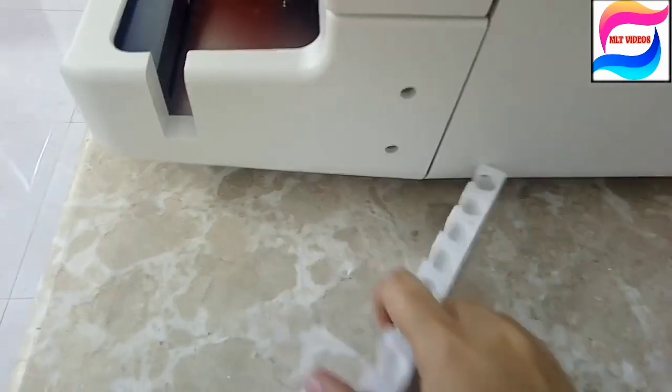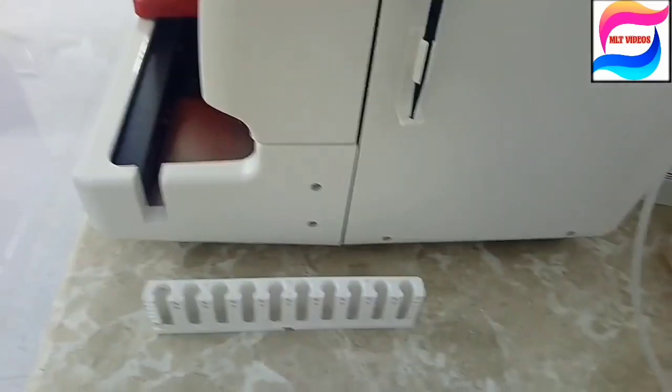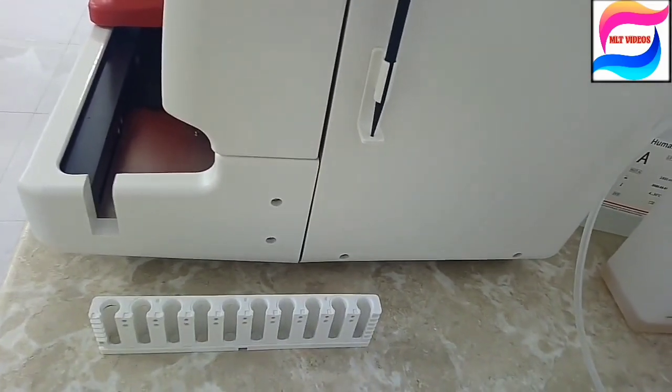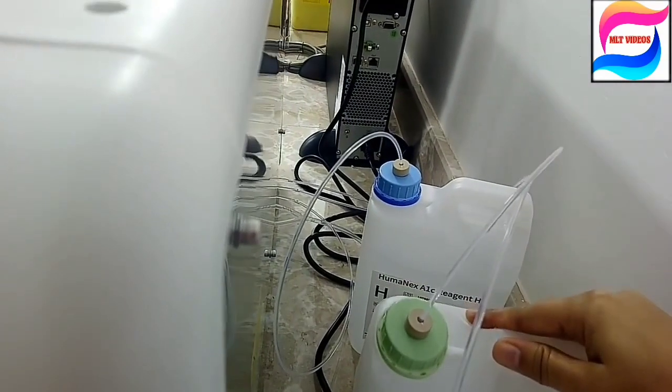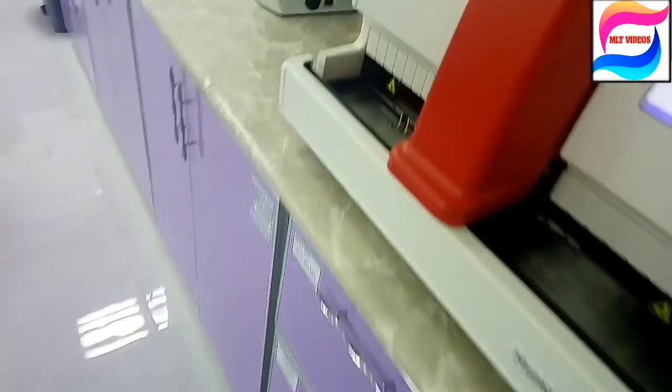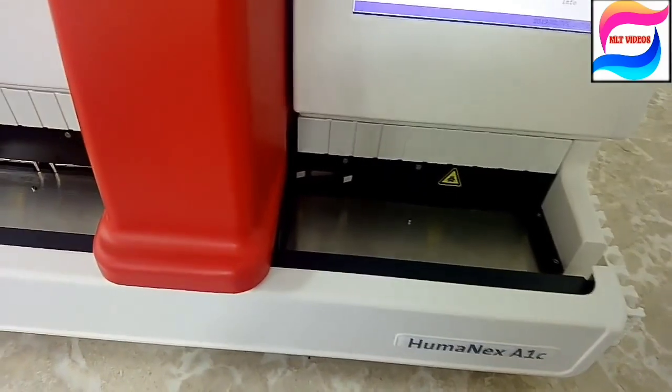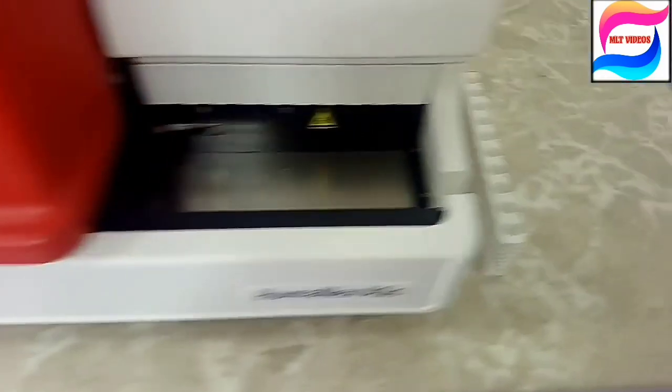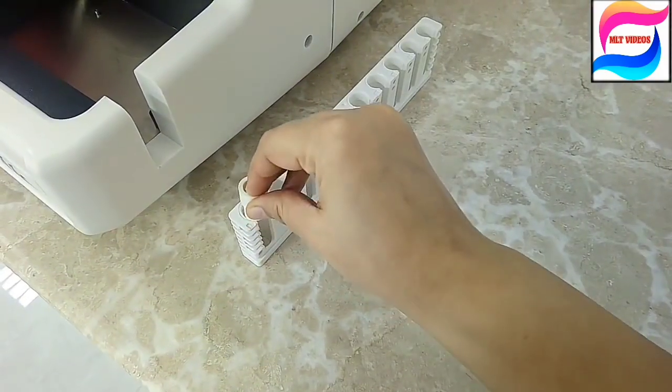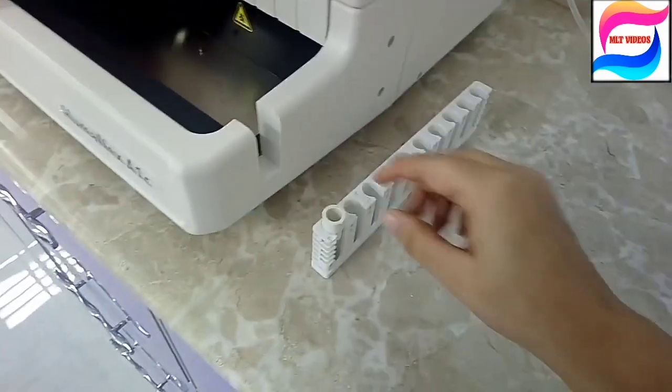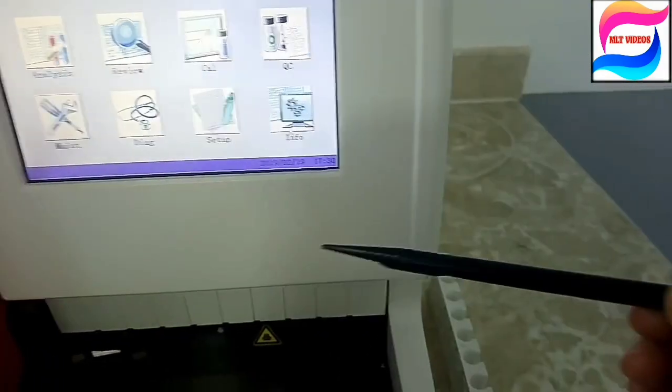This rack is used. We will keep the samples in this rack. There are two types of samples we will use. For example, as we know, we need EDTA sample whole blood. And next sample is if sample is in very less quantity or controls that we will dilute with H reagent and we will keep in Eppendorf vial. Then we will run machine. In this cup we will keep Eppendorf vial and machine automatically will detect by the cup and by the EDTA tube. Machine automatically will detect, so we no need to write the type of sample.